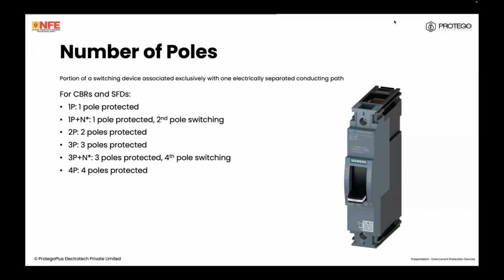The thing is, one pole plus neutral and three pole plus neutral are commonly used terms. However, the correct terms as per the standards are two pole and four pole. For a one pole plus neutral, the correct term would be two pole with one pole protected and one pole switched or unswitched, depending on the protected device. And for three pole plus neutral, it would be a four pole protected device with three poles protected and one pole switched or unswitched. So that's just for your reference.